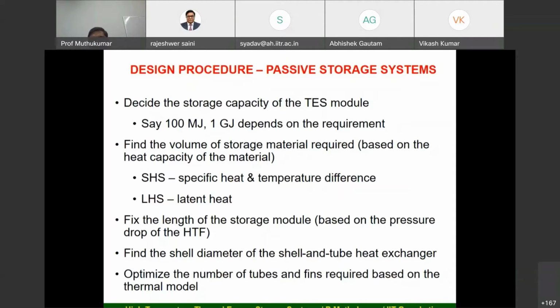Once you finalize the storage capacity, you need to find the volume of the material. In the sensible heat system, to find the volume, we need the temperature difference and specific heat of the material. Once you know the specific heat and temperature difference, you can find the storage capacity: Q is equal to m Cp delta T. Then the mass can be found out.